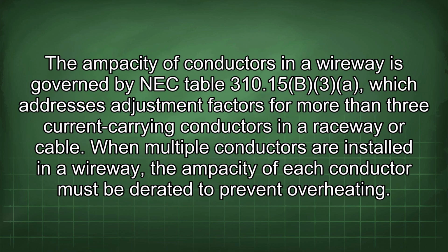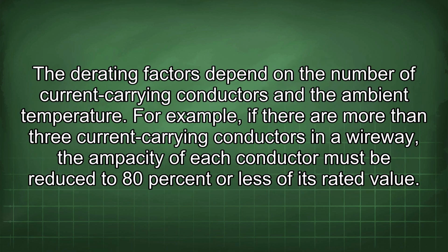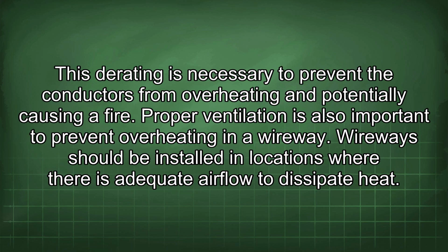The ampacity of conductors in a wireway is governed by NEC Table 310.15(B)(3), which addresses adjustment factors for more than 3 current carrying conductors in a raceway or cable. When multiple conductors are installed in a wireway, the ampacity of each conductor must be derated to prevent overheating. The derating factors depend on the number of current carrying conductors and the ambient temperature. For example, if there are more than 3 current carrying conductors in a wireway, the ampacity of each conductor must be reduced to 80% or less of its rated value. This derating is necessary to prevent the conductors from overheating and potentially causing a fire.